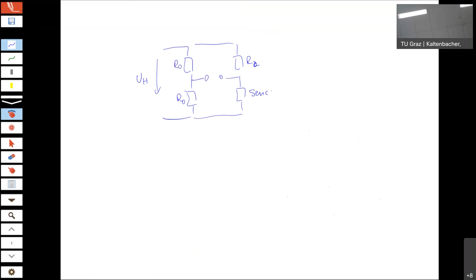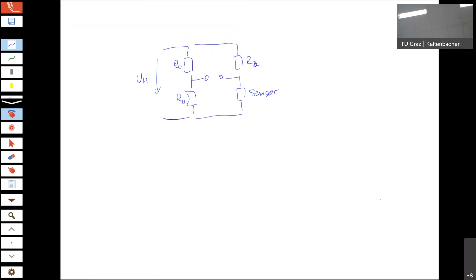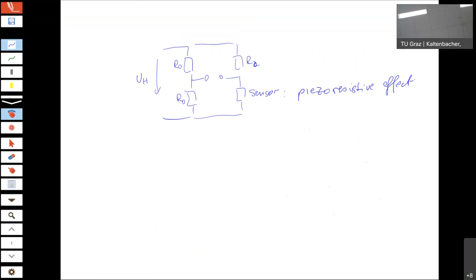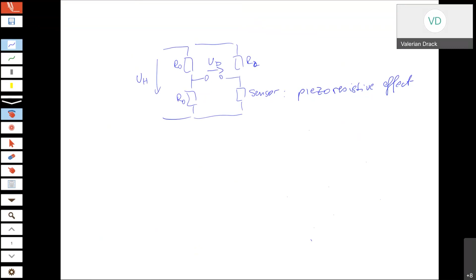This Wheatstone bridge is as follows. You provide here a voltage, and what you have here are fixed resistors with the same value, and here is your sensor. The Kulite sensors have the piezoresistive effect, so by the fluid pressure they change the resistivity. Out of the change of resistivity, you get the change of this voltage here. This voltage then goes into a preamplifier, and then you have filters and whatever you have there. That is the main signal processing of this sensor, and the sensor itself is piezoresistive.